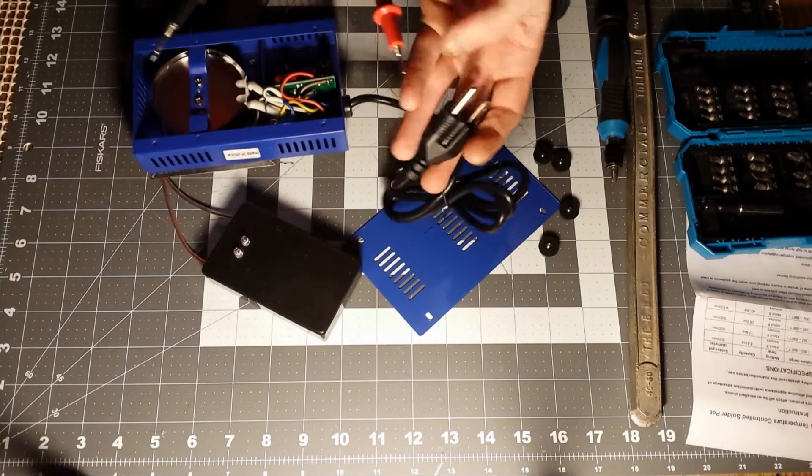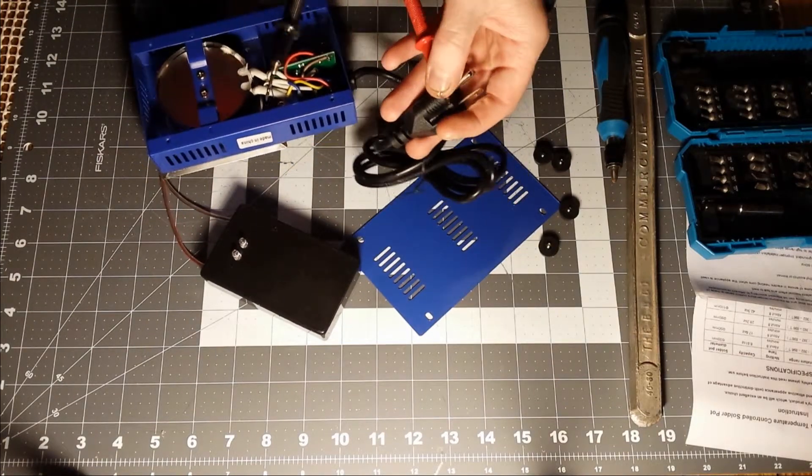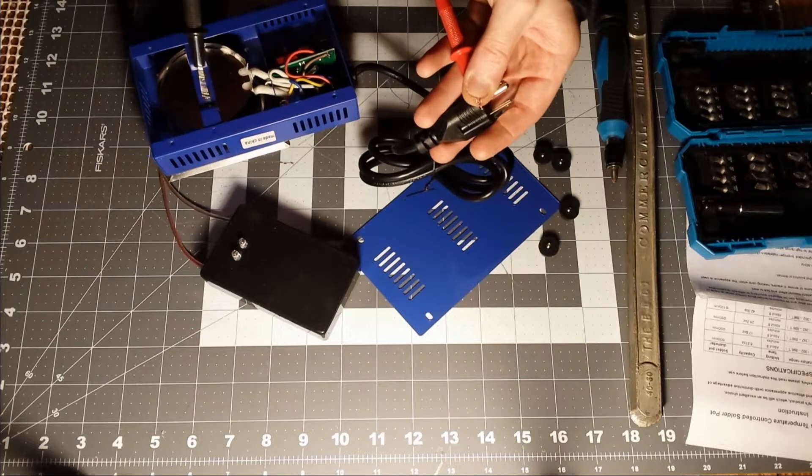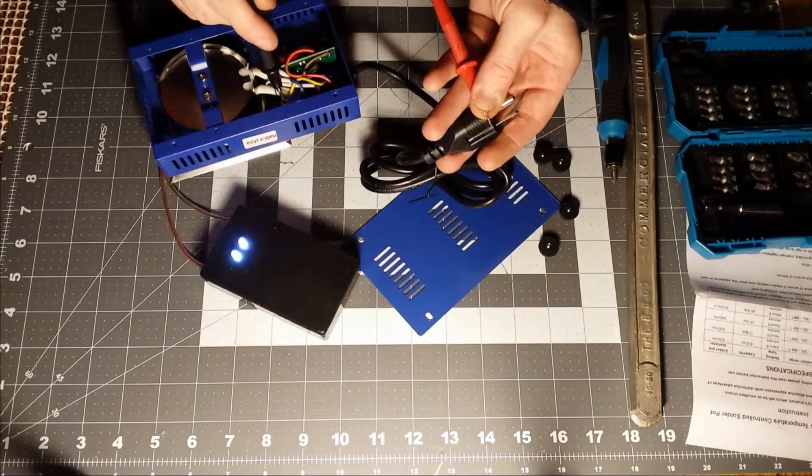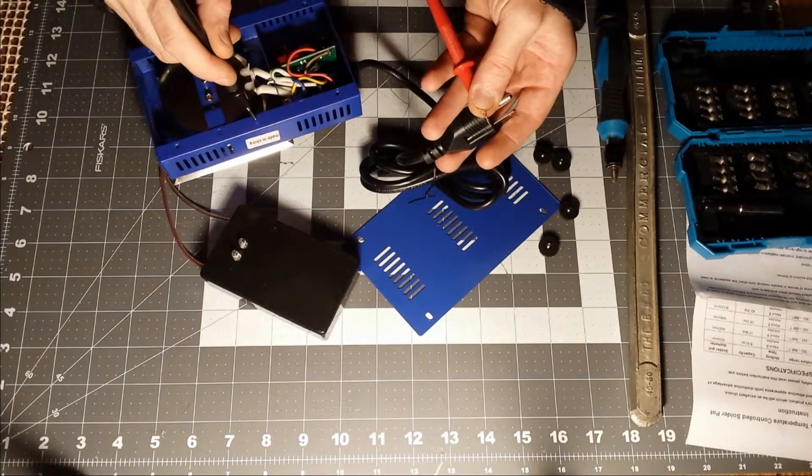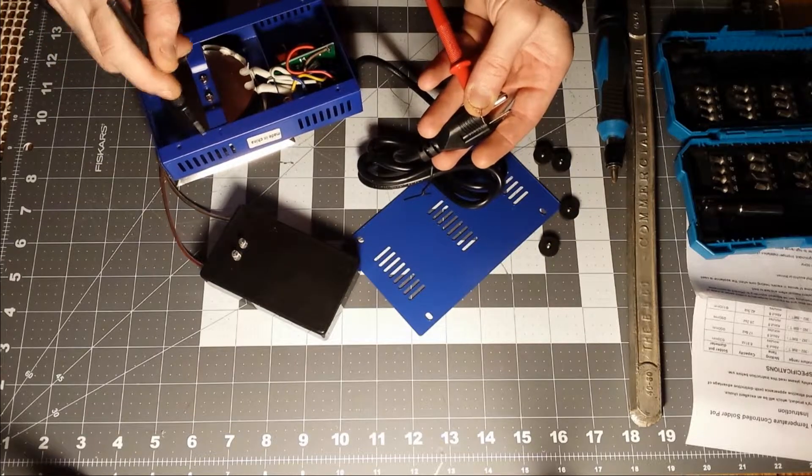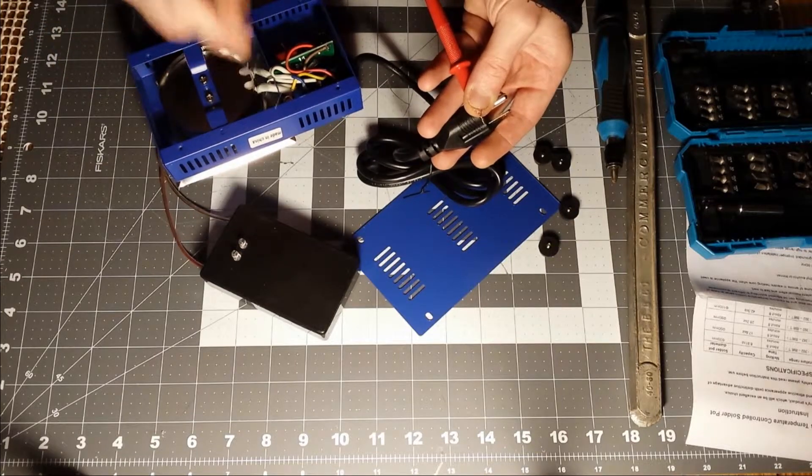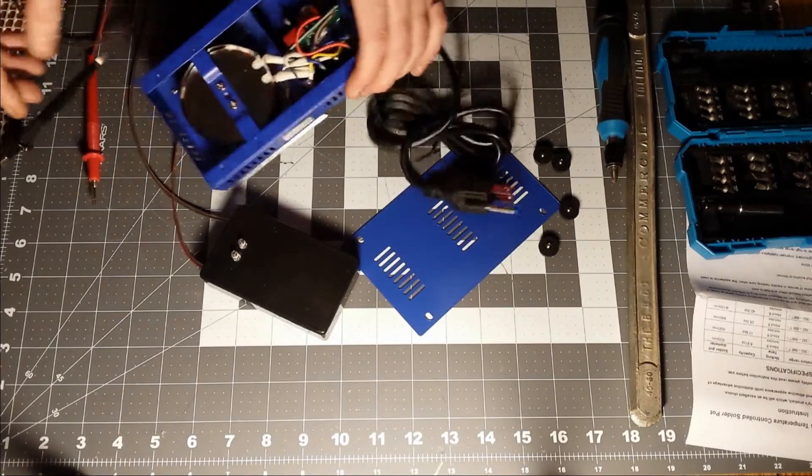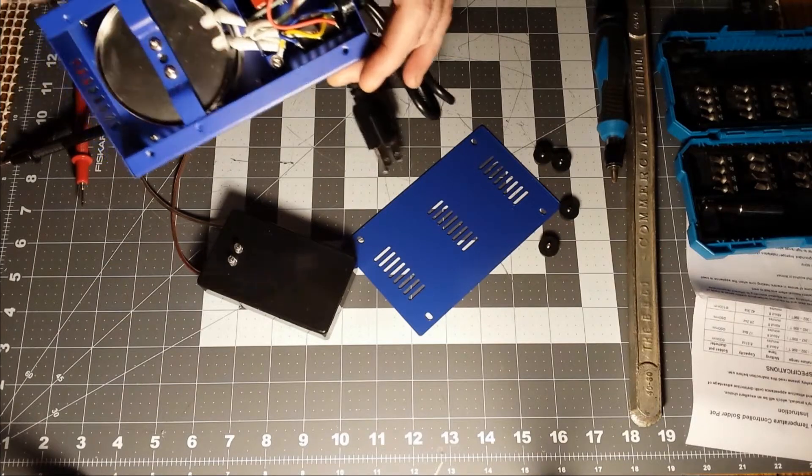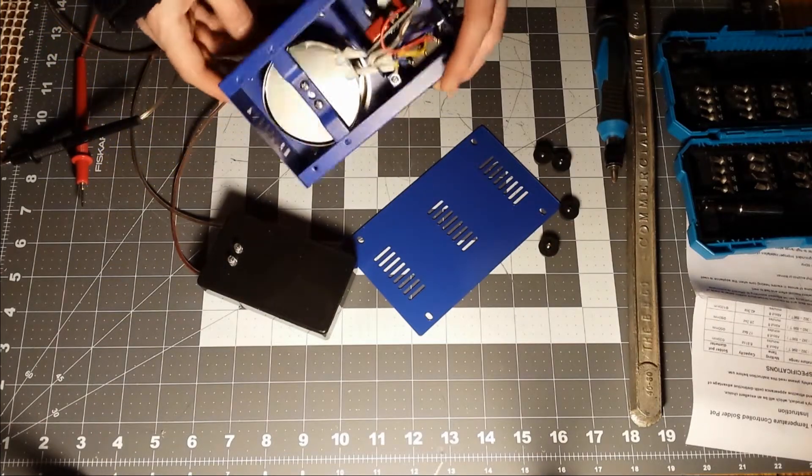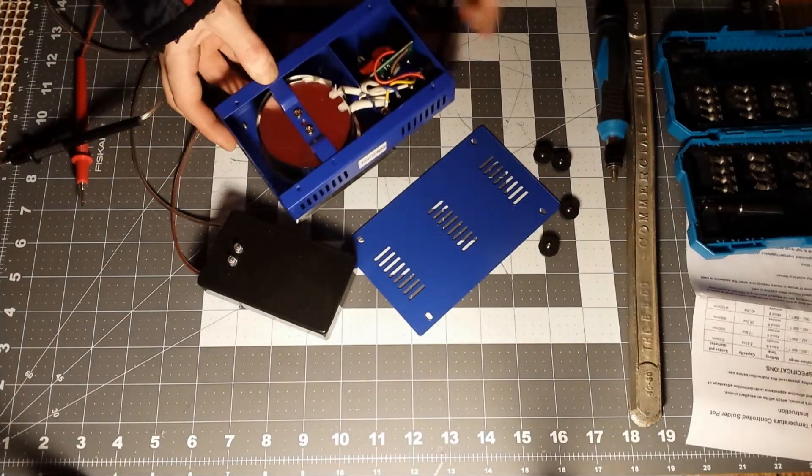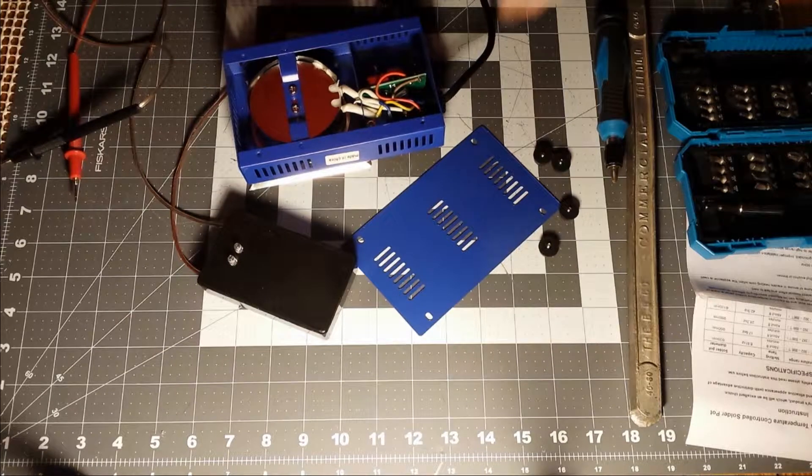So the ground leg on the plug here, go into the screw, it's no problem. If I go into the metal case, nothing. So it's effectively not grounded until I take that screw off and rub off the paint and put it back on. So there's one issue to solve already.